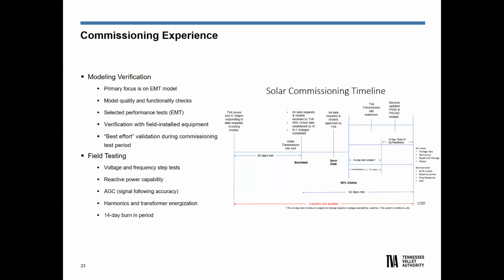That includes field testing that has voltage and frequency step tests, reactive power capability. We send them signals from the EMS system to make sure they can follow the AGC correctly, and then we give them a rating on how well they can follow the AGC. And we are testing the whole time with equipment on site for harmonics and transformer energization. Again, just making sure during that 14-day period that we have the highest quality interconnection that we can get from the folks there. You can kind of see our solar commissioning timeline there to the right.